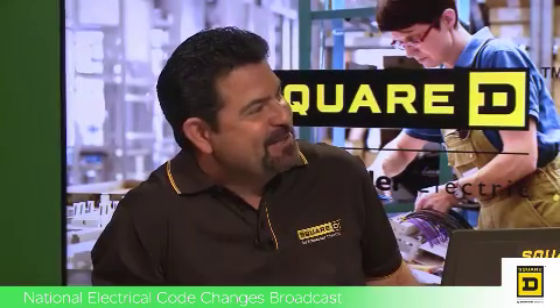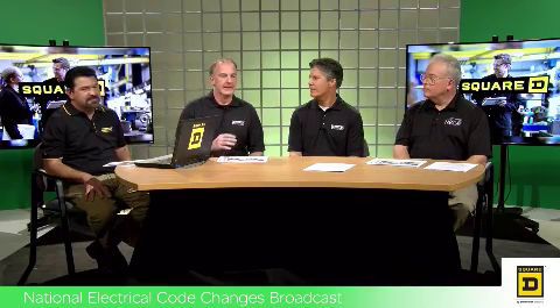Great, thank you, Chad. So Alan, next topic, Section 408, service panel boards. Okay, so this is the barrier for the incidental contact. So in 408.3, what we've done is we've actually added language, added panel boards to what's already in place with regard to incidental contact for switchboards and switchgear. So this adds shock protection on the line side of the overcurrent device.